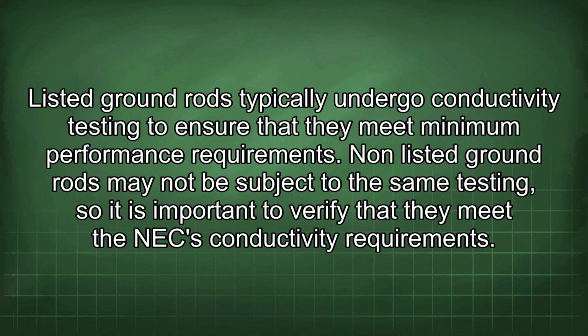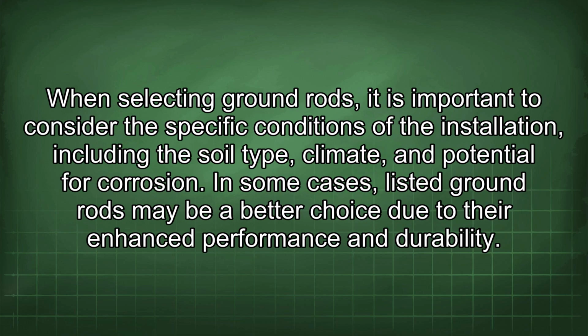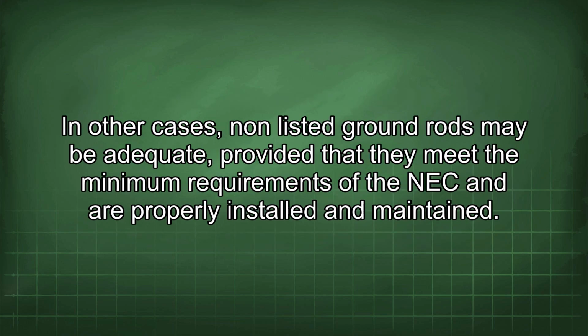Listed ground rods typically undergo conductivity testing to ensure that they meet minimum performance requirements. Non-listed ground rods may not be subject to the same testing, so it is important to verify that they meet the NEC conductivity requirements. When selecting ground rods, it is important to consider the specific conditions of the installation, including the soil type, climate, and potential for corrosion. In some cases, listed ground rods may be a better choice due to their enhanced performance and durability. In other cases, non-listed ground rods may be adequate, provided that they meet the minimum requirements of the NEC and are properly installed and maintained.